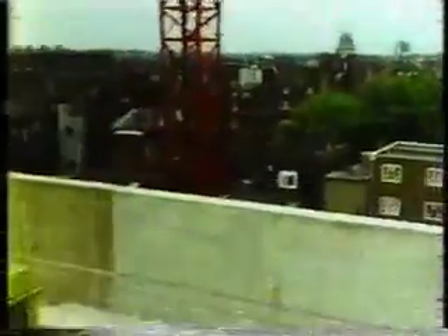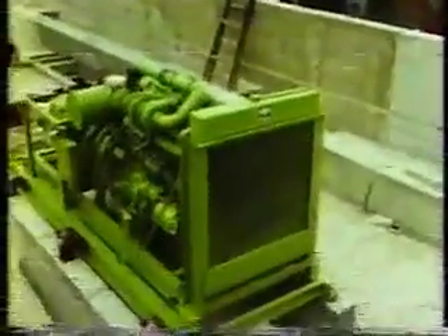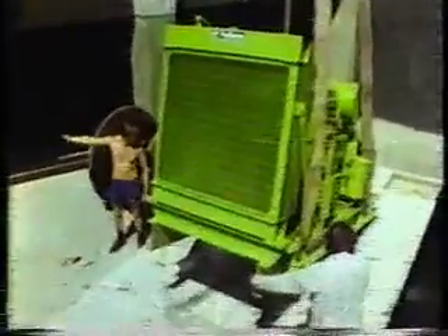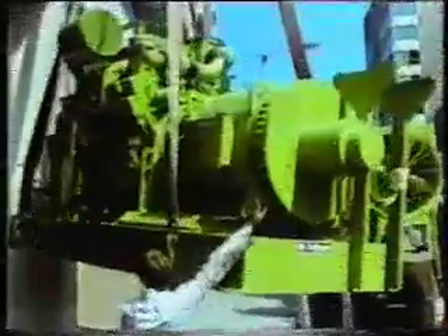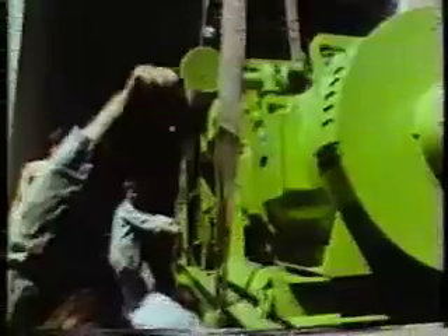They're able to start up larger electric motors than would be normally expected. They will cope with short-circuit fault conditions without damage and rapidly recover voltage after sudden heavy load changes. They accept 100% out-of-balance loading and still retain a good voltage regulation, something few other machines are able to claim.